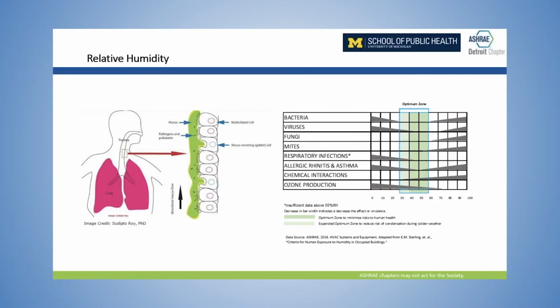And interesting to note, the relative humidity range that's ideal for humans is the opposite for pathogens, right? So we like for it to be, really ideally, between 40% and 60%. We have a little fudge factor here in Michigan because it's really dry in the wintertime, so we take it down to 30. But pathogens don't like that range. They prefer to be outside of it. They prefer to be less than 20 or more than 65% relative humidity.